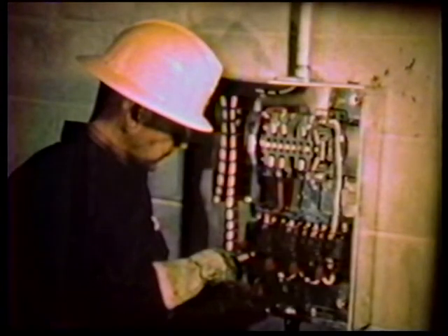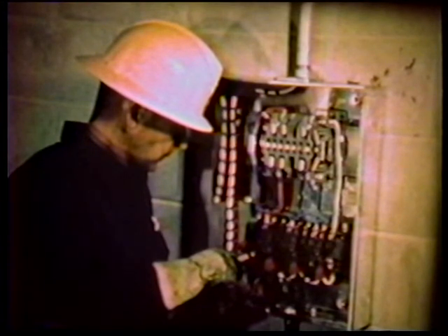In instrument transformer rated meter jobs, test switches are another hazard. Close proximity of line and grounded terminals call for special care when connecting leads or using tools. When working above test switches, be careful not to drop metallic parts on the test switch. The result can be a serious flash. Make sure all current circuit connections are tight so no open circuits are possible. Again, high voltage buildup can result and you may receive a shock.